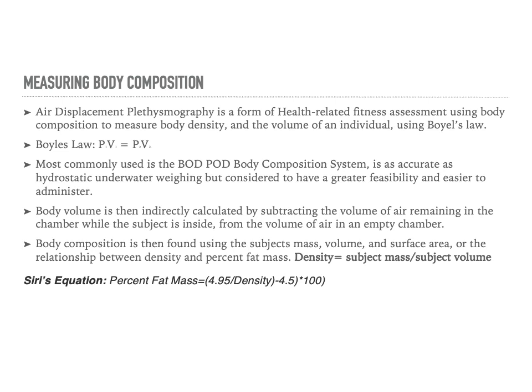Density is the subject mass over the subject volume. The BODPOD body composition system uses its own system of equations known as the Siri equation, stated as: (4.95 / density − 4.5) × 100, to calculate the percent fat mass.